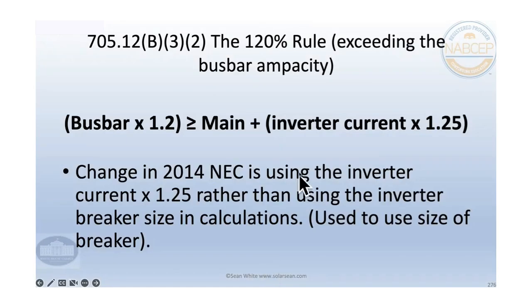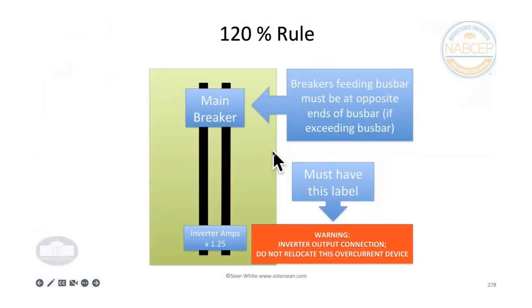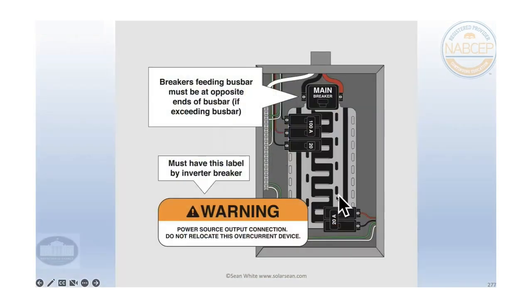And then the 120% rule, which I'd imagine you're probably all very familiar with. What we have here is the main breaker. And so we take the bus bar times 1.2. I like using a 100 amp bus bar times 1.2 is 120 amps. Subtract the 100 amp main breaker, and that leaves us 20 amps would be the largest inverter breaker that we could have, which is 125% of inverter current. So that would be a 16 amp inverter or less. That is what you could fit, and you would have to put them at opposite ends.